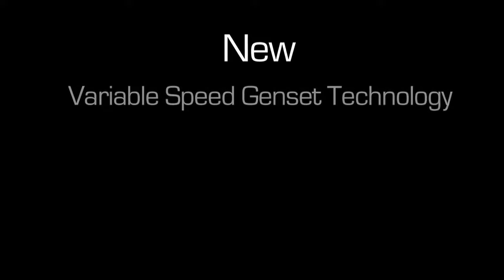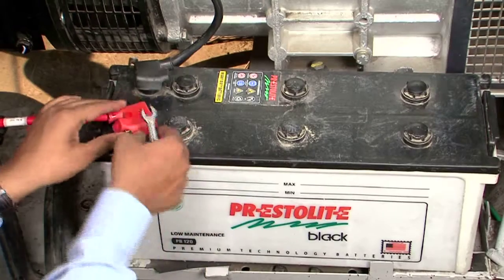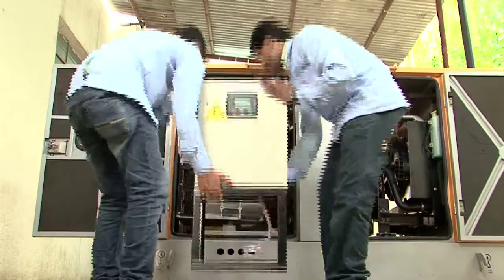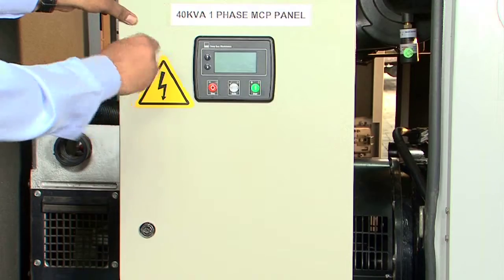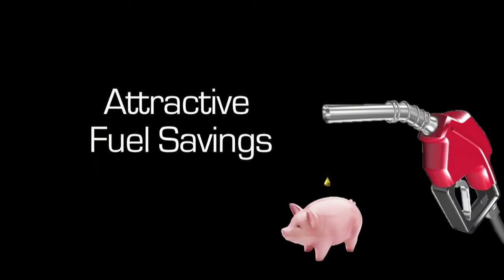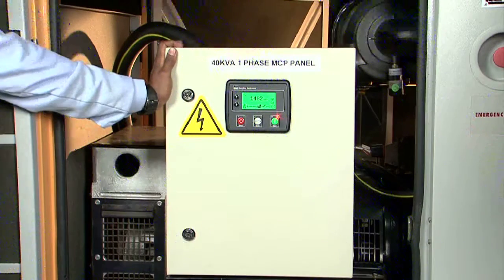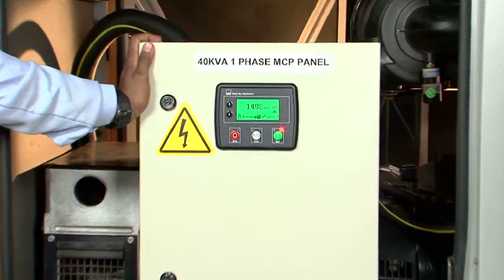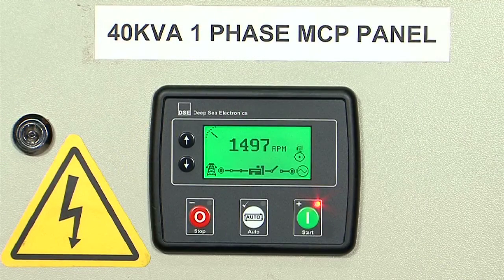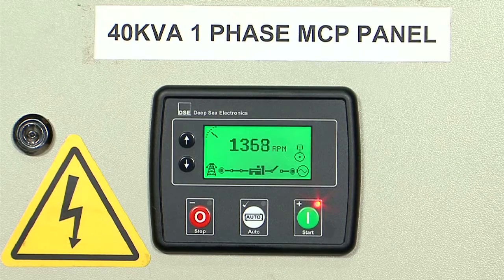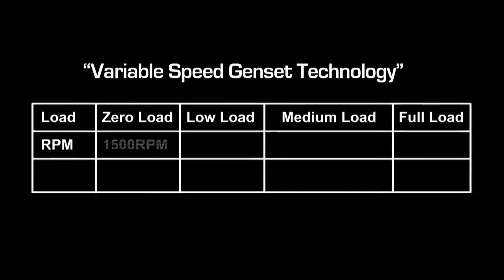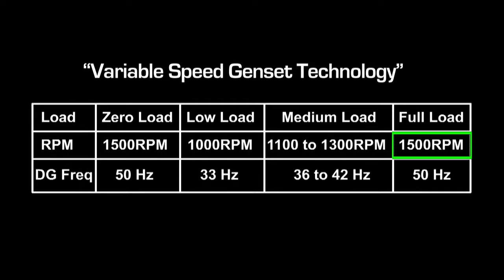To resolve this issue, the new technology is designed to avoid fixed speed operation by making use of variable speed operation. The new technology brings attractive fuel savings. Let's find out how. A variable speed genset is a load-sensitive DG that changes its speed depending on the load condition. At full load condition, it runs at the rated 1500 RPM. When the load on the DG reduces, it runs at optimum speeds which are lower than 1500 RPM, thus improving the part load fuel efficiency of the engine.